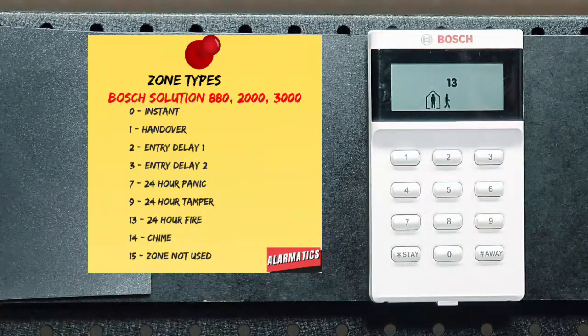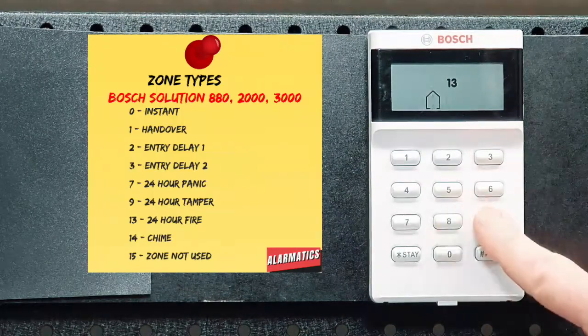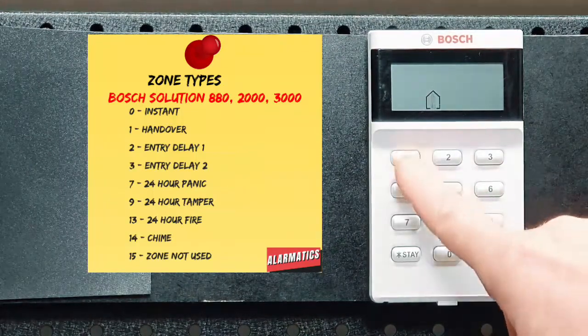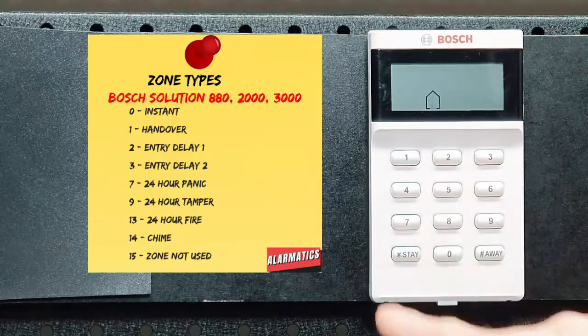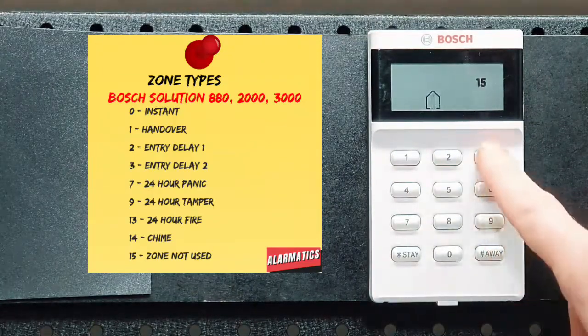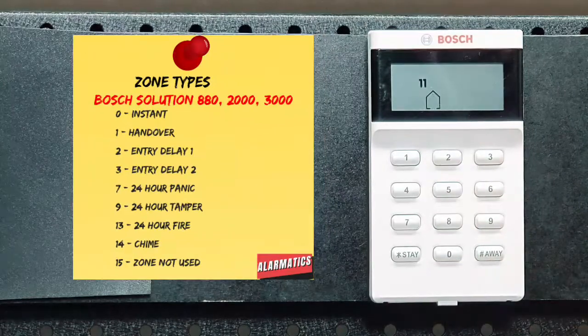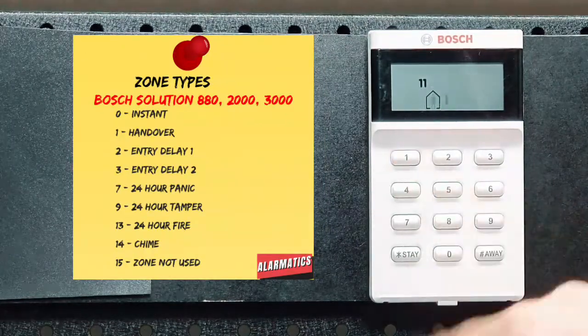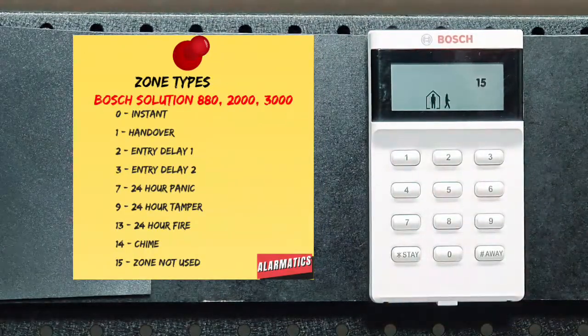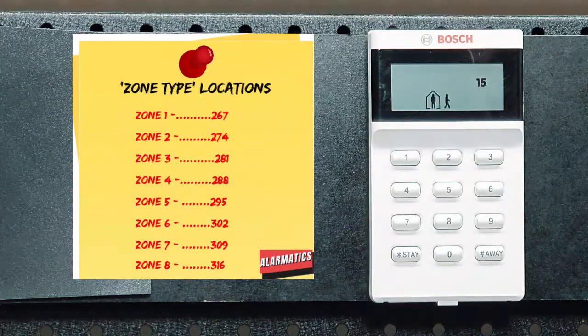Now, zones 7 and 8 are not going to be used. So any zone that's not used on the system, you give it a zone type of 15. That means it won't display on the code pad and the system will ignore it. So let's go down to zone 7. We'll make that a 15 and save it. And let's go to zone 8, which is 316. I'm going to make that a 15 and I'm going to save it. And that's how we program our zone types.